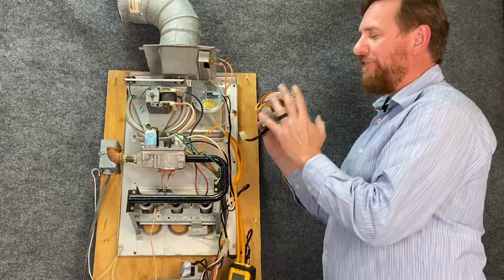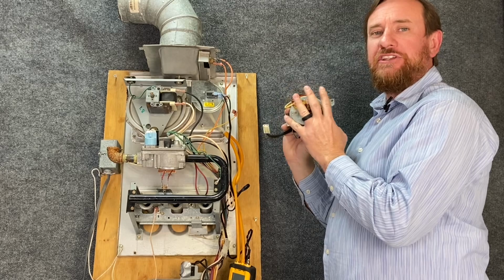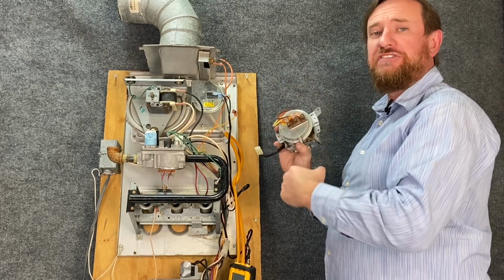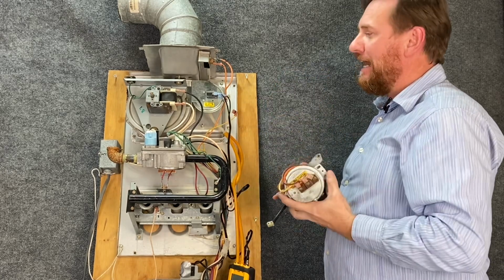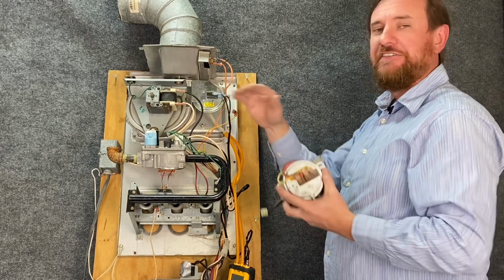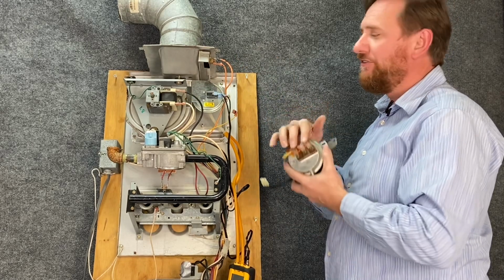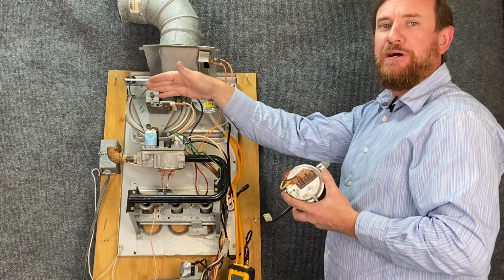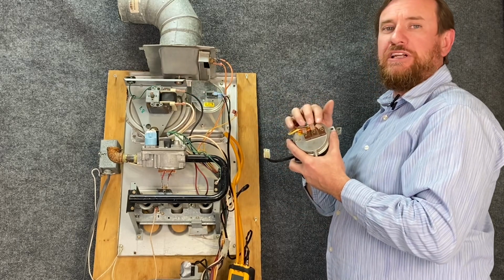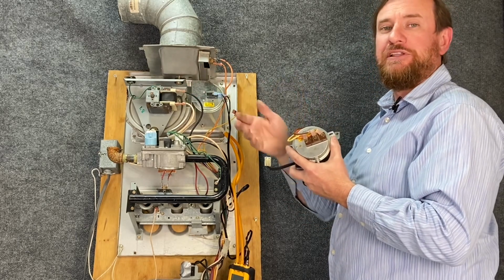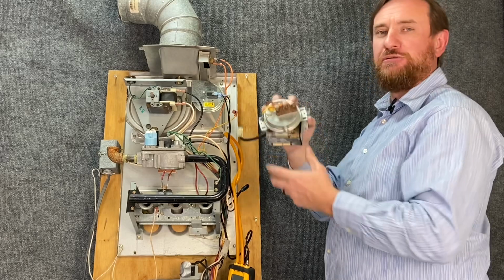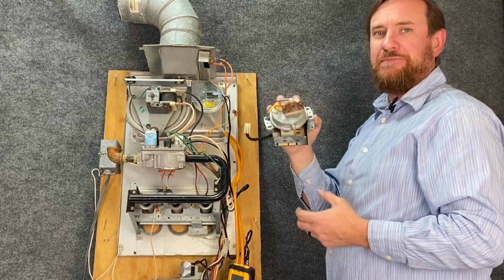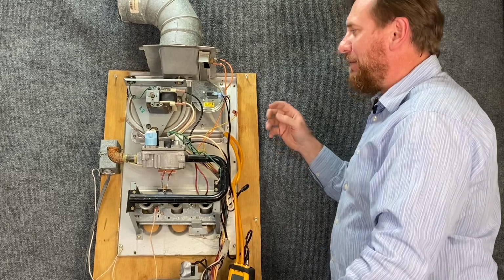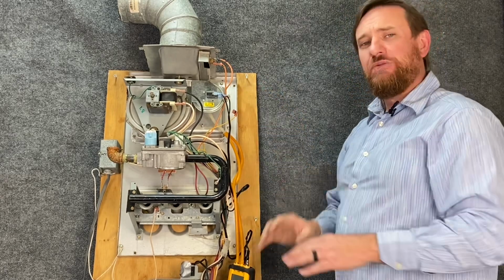The control board for this particular unit wants to know that the switch is for sure closed and the switch is for sure open. In other words, right now the system is off. It wants to know that that switch is closed, and when the system came on and pulled the proper vacuum, the normally closed would open, the normally open would then close. Without a doubt, the control board would know that this switch hasn't been bypassed. I have seen people try to bypass these, and you never want to do that.